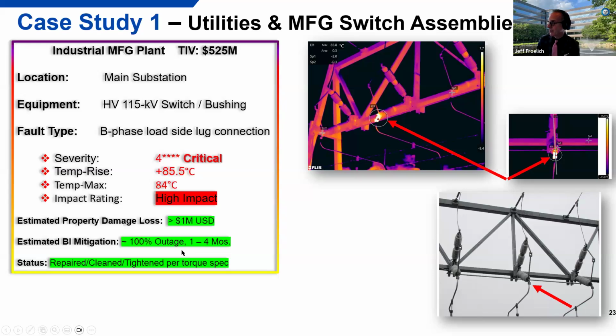Of course, thermography is a key item. And these things can lead to power losses. They can lead to cable degradation. High humidity will enhance this potential. Mitigating would be making sure you're using specialized insulation, larger conductors, things of that nature, proper cleaning and maintenance. We're showing an 85°C delta. So this one's a significant showstopper. It shuts down the whole operation. Could be $1 million a day. Depends on how much product they're producing, but it's a big one.